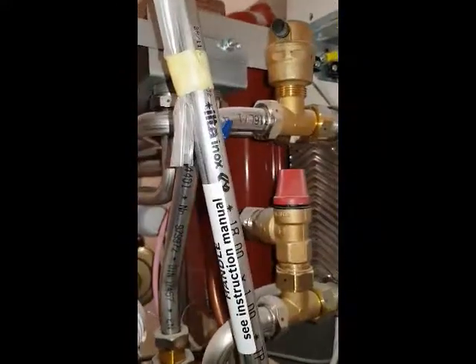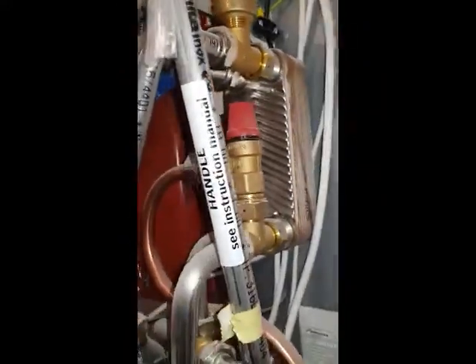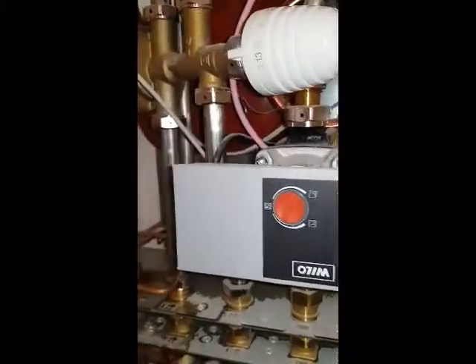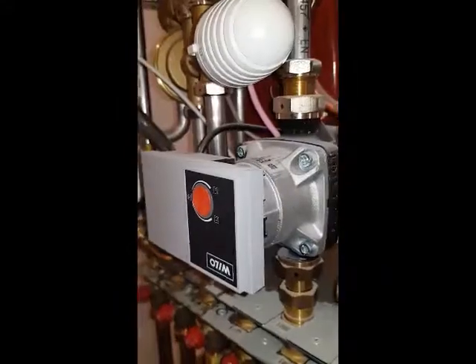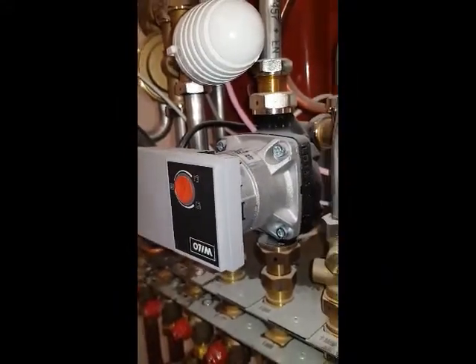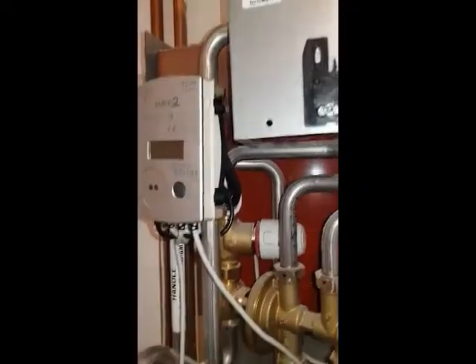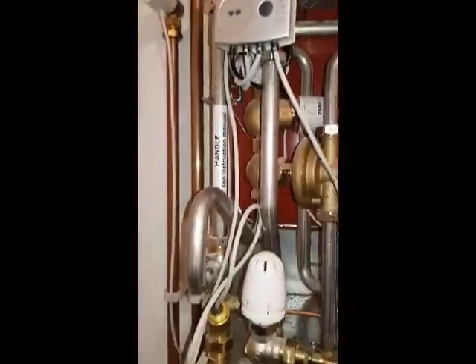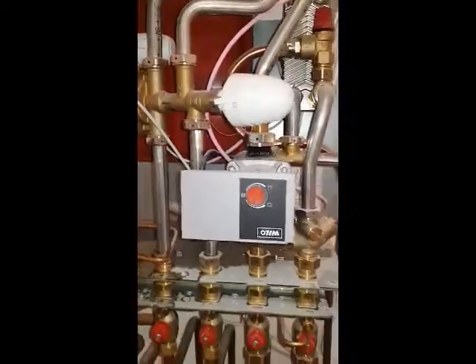Open the PRV and take the pressure off, so the leak has now stopped. This is the pump for the heating circuit. And that's the auto air vent. It's got these other additional controls which are like thermostatic controls to keep the heating at the correct temperature.